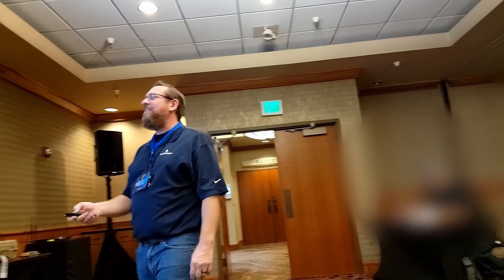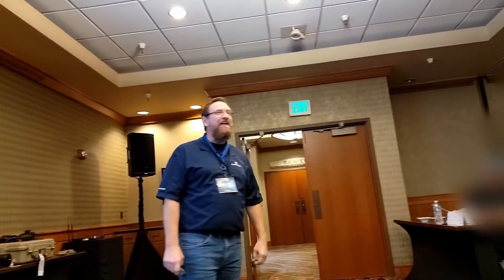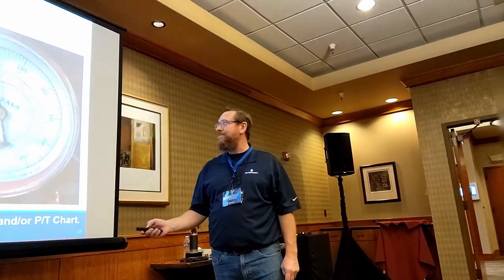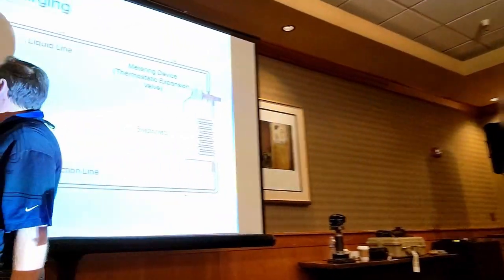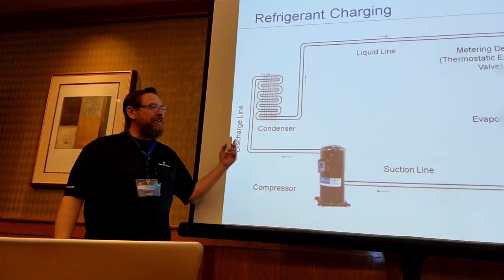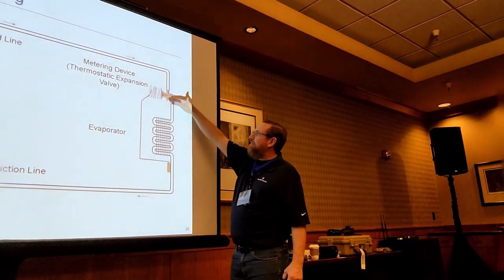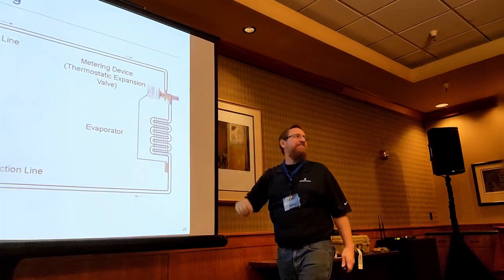Let's do the next one — CO2, R744. At 500 PSIG — that's a crazy high number — the saturated temperature is 33.7°F. So where on the refrigeration cycle would that be? That would be somewhere in the middle of the condensing section. When it was at 31-point-something degrees, that's from the metering device through most of the coil — where it's saturated, where liquid and vapor are together.